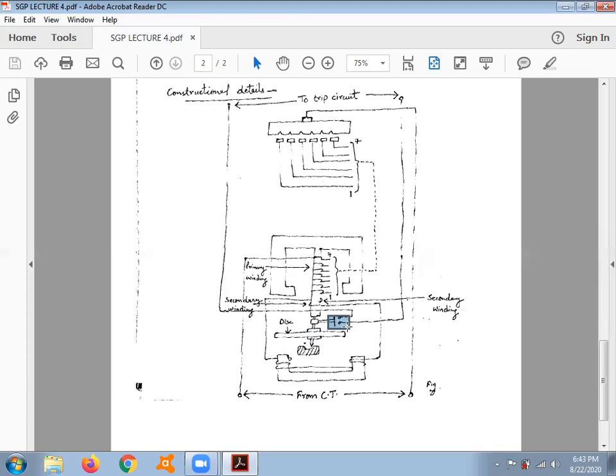So how will the disc rotate? There are two types of torques that the disc will experience. One is known as the restraining torque and the other is known as the driving torque. Restraining torque is the torque that holds the disc in its stationary position. Driving torque is what shifts the disc at a particular angle so that the trip circuit gets closed.